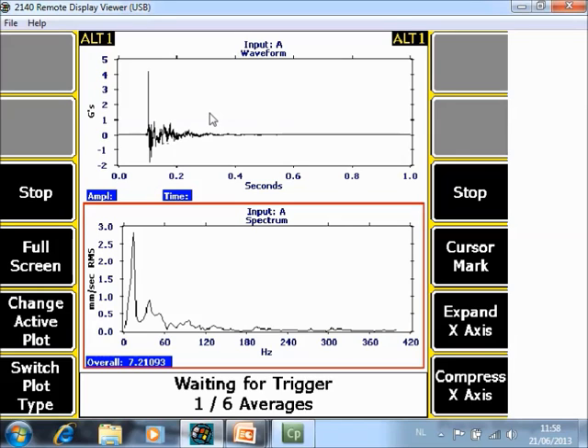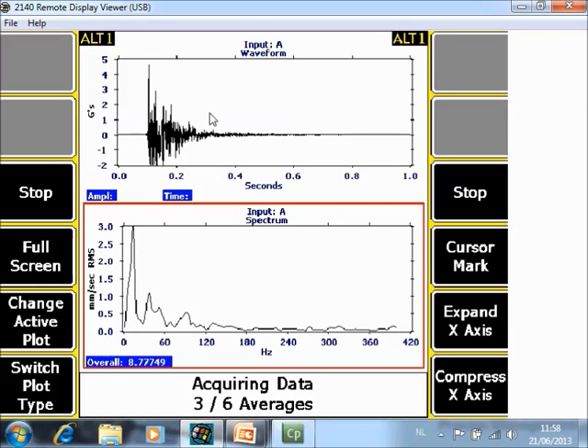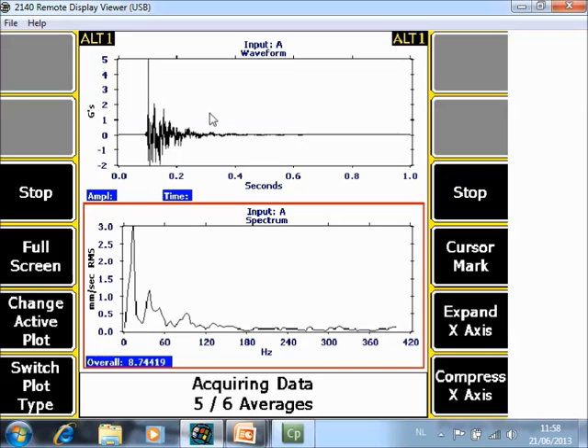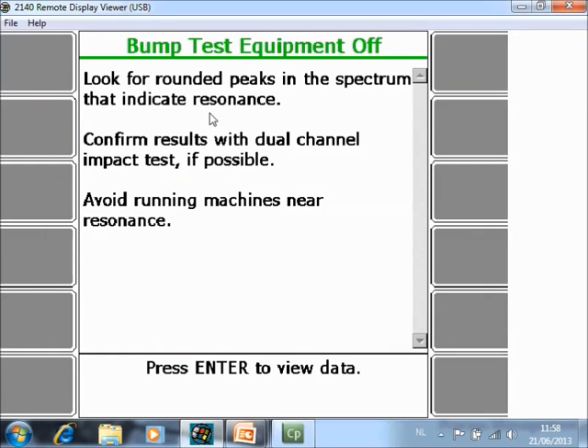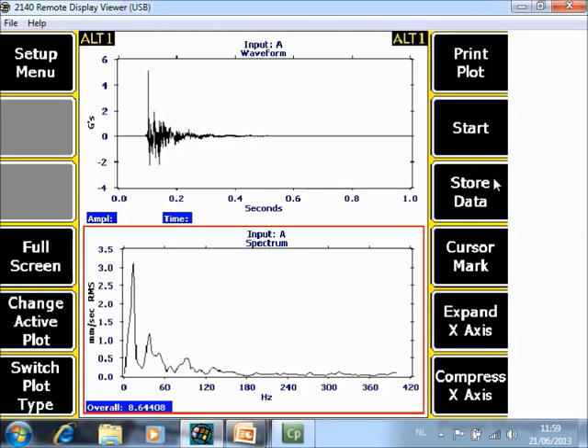Now I impact the machine a second time, three times, four, five, six. And it's done. To view the data press enter. Now you see the impact here and the average spectrum. You can store the data in the job mode by using store data F9.